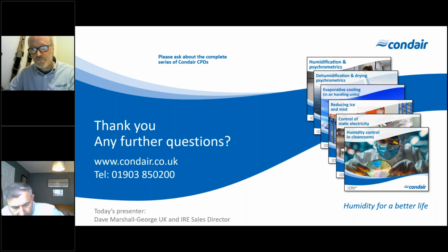Yes, I can. This is the distance, typically with steam, where steam leaves the steam pipe to where it's fully mixed with the air. So you will see a visible plume of steam coming off that steam pipe. Now, the length of that plume, or the absorption distance, is critical, because if we put any object in the way of that before all the steam has evaporated, we can get condensation forming. So you'll get water in the air handling unit.